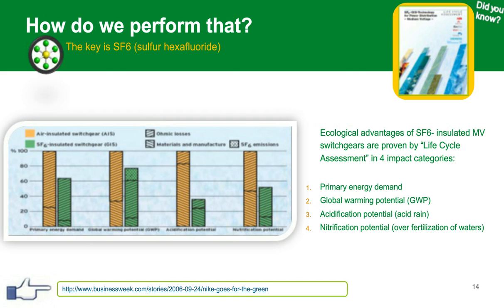There have been studies, however, like this one cited on this slide, which show that over the total life cycle, considering particularly hermetically sealed, but not only hermetically sealed gas-insulated switchgear, that over time, gas-insulated switchgear actually contributes less to several different factors, including global warming potential, acidification potential, and the nitrification potential, than some open-air switchgear. So although we utilize SF6, which is a greenhouse gas, it also helps reduce the effect of the switchgear on the environment as well. That's one of the other reasons why we still use it in the industry.